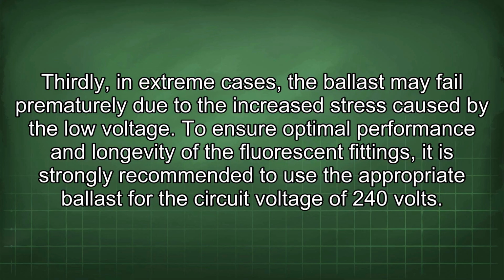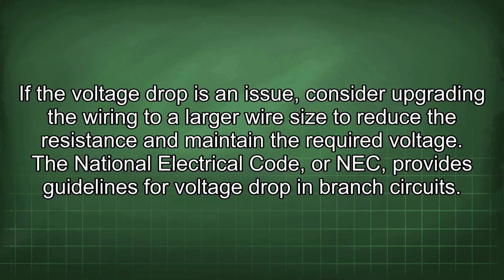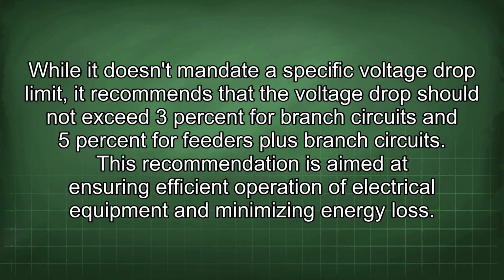To ensure optimal performance and longevity of the fluorescent fittings, it is strongly recommended to use the appropriate ballast with a circuit voltage of 240 volts. If the voltage drop is an issue, consider upgrading the wiring to a larger wire size to reduce the resistance and maintain the required voltage. The National Electrical Code, or NEC, provides guidelines for voltage drop in branch circuits. While it doesn't mandate a specific voltage drop limit, it recommends that the voltage drop should not exceed 3% for branch circuits and 5% for feeders plus branch circuits. This recommendation is aimed at ensuring efficient operation of electrical equipment and minimizing energy loss.